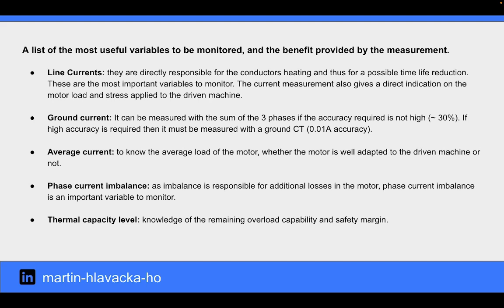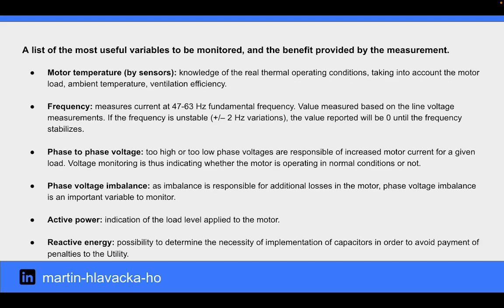Phase current imbalance. As imbalance is responsible for additional losses in the motor, phase current imbalance is an important variable to monitor. Thermal capacity level: knowledge of the remaining overload capability, and a safety margin. Motor temperature: knowledge of the real thermal operating conditions, taking into account the motor load, ambient temperature, and ventilation efficiency.